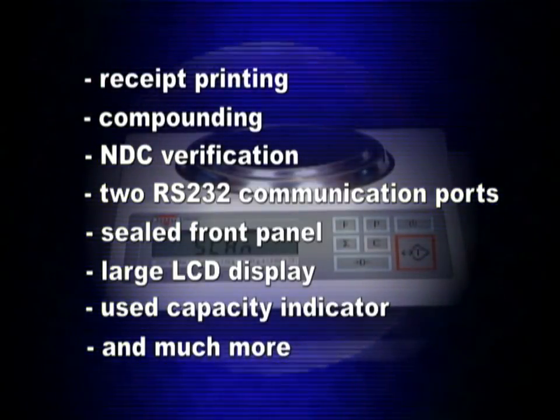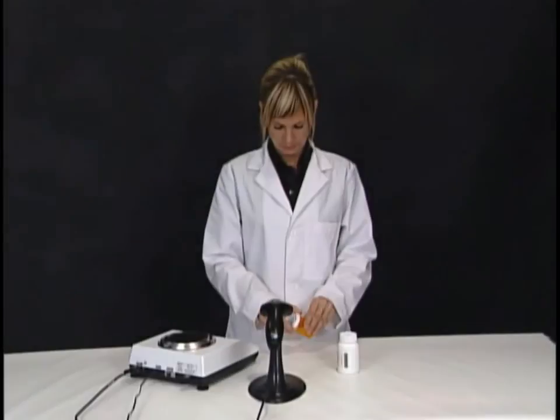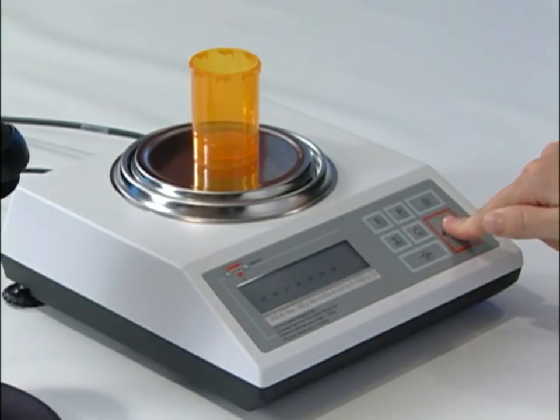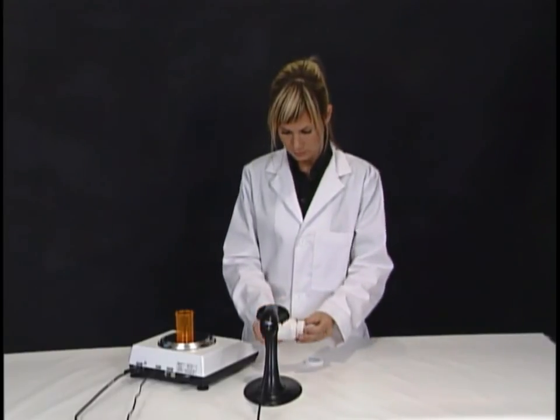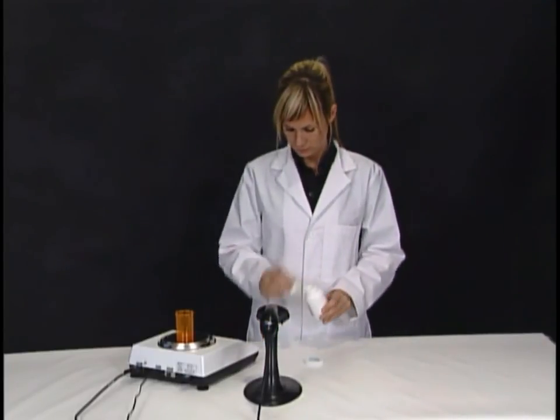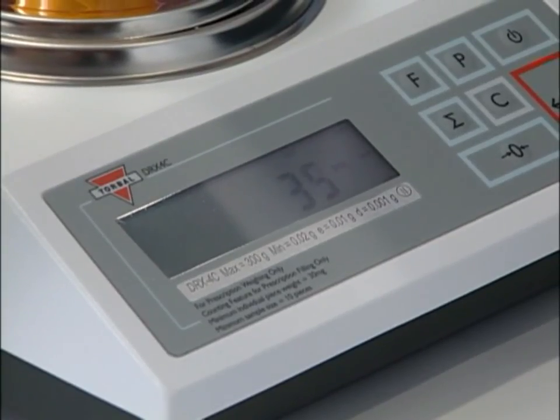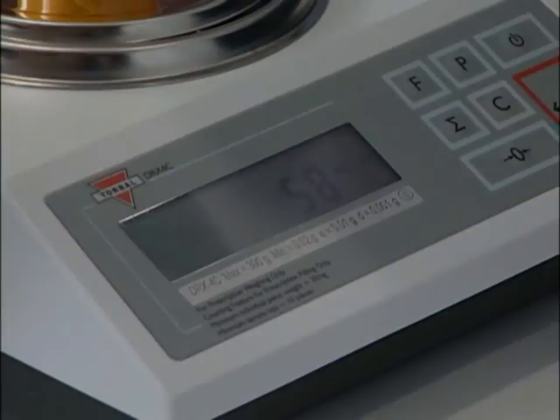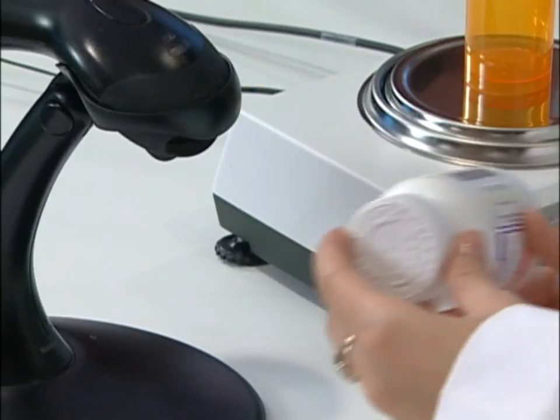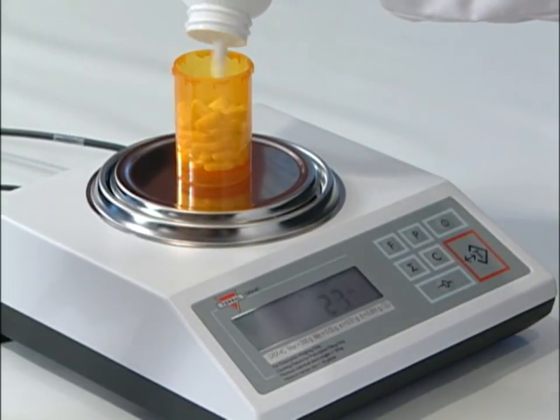Pill counting with the DRX 4C is also an easy three-step process. If a drug has been previously stored in the scale's database, simply place a vial on the pan and tare it by pressing the T key. Then scan the barcode located on the supply bottle. Once the barcode is scanned, the scale indicates to begin filling the pills. Pills are counted as fast as they are poured into the vial. Step 1: Tare the container. Step 2: Scan the supply bottle. Step 3: Pour the pills into the vial to achieve the desired count.